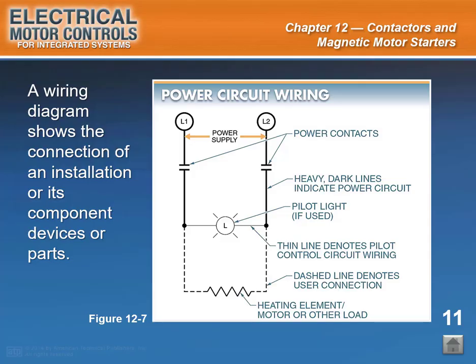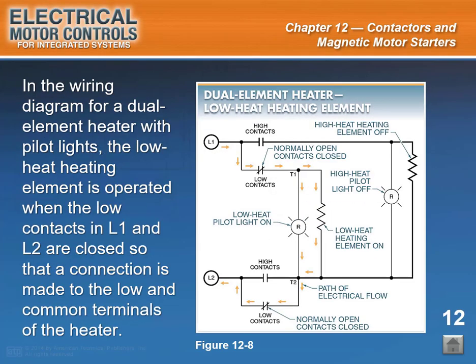An understanding of wiring diagrams is required because an electrician may be required to make changes in power circuits as well as in control circuits. End of slide 11. Start of slide 12. Slide caption: in the wiring diagram for a dual-element heater with pilot lights, the low-heat heating element is operated when the low contacts in L1 and L2 are closed so that a connection is made to the low and common terminals of the heater. See figure 12-8.